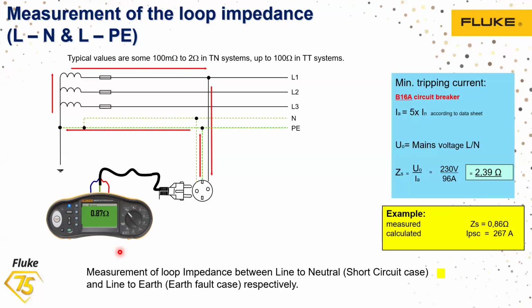Now let us assume that there is a 16 ampere MCB, which is a circuit breaker, connected in the electrical installation. What should be the resistance, that is the impedance value, and how much should be the prospective short circuit current? If it is a 16 ampere MCB, in general it is between 5 to 10 times. So we will take 5 times the current, which is 96 ampere, and the nominal voltage between phase and neutral is 230 volts. So the impedance is directly calculated here. Under this condition, the resistance should be close to 2.39 ohms.